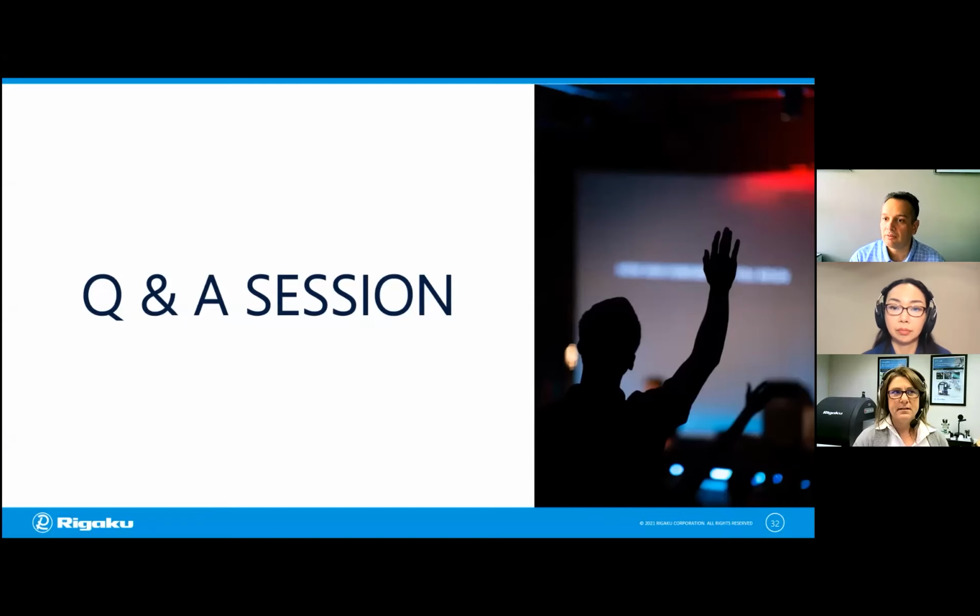And I think I might not have answered the first question. The first question is, can we control these settings, right? Absolutely. Also the detector settings, like binning and distances. Absolutely, yes. This is doing an automatic reconstruction, but you can do this manually, where you can bin 1 by 1, 2 by 2 or greater. It just depends on the sample that you're imaging.